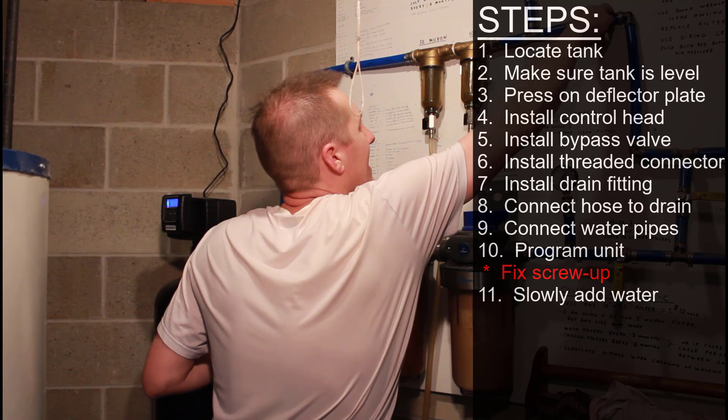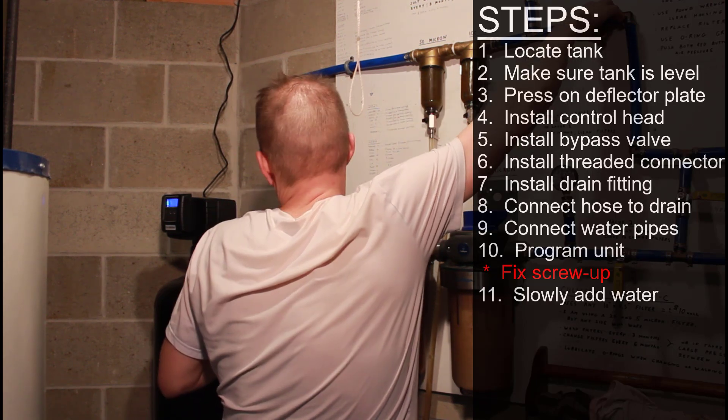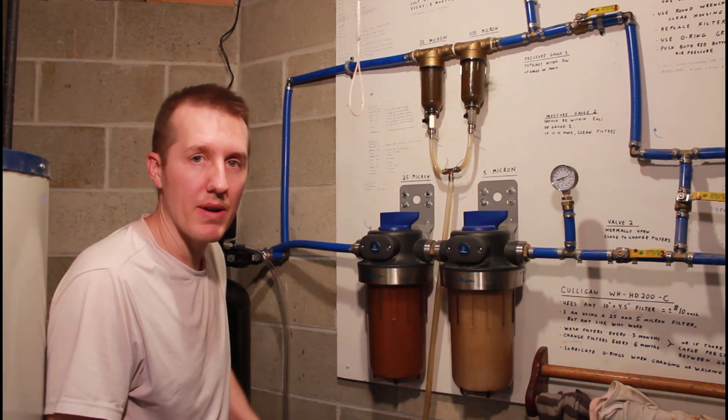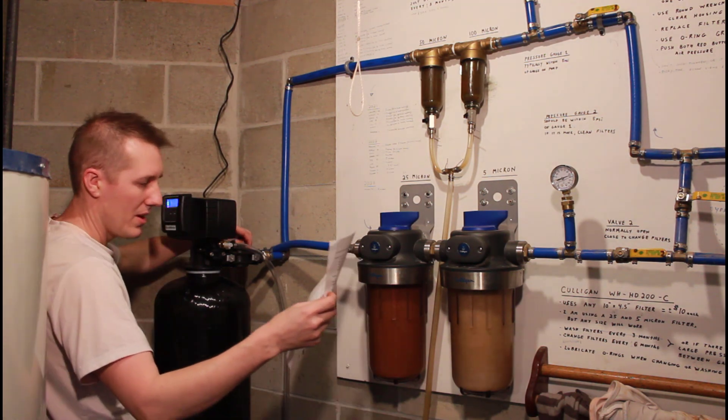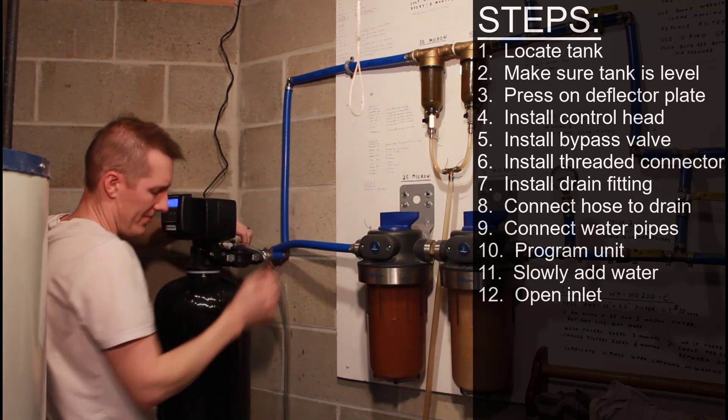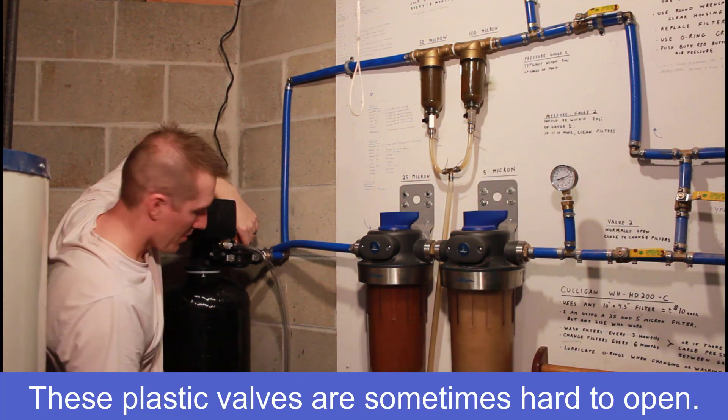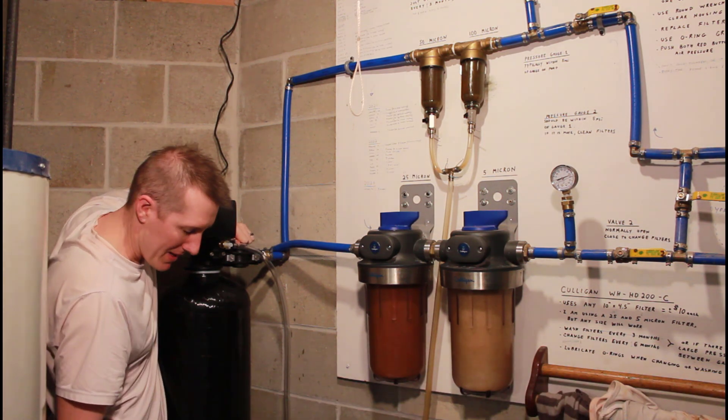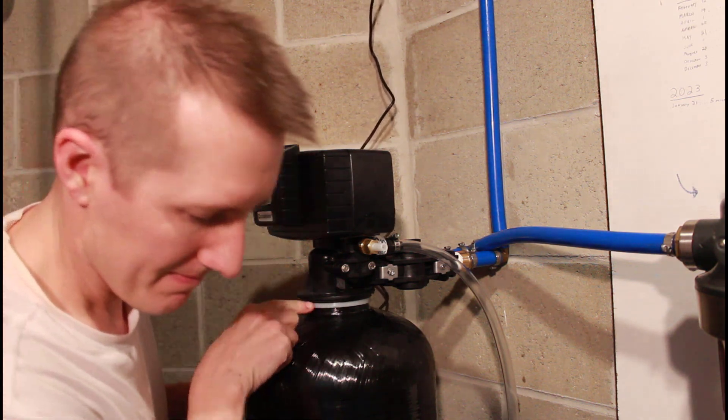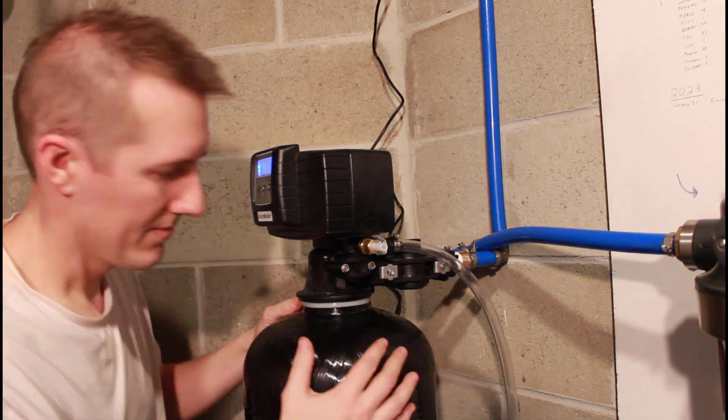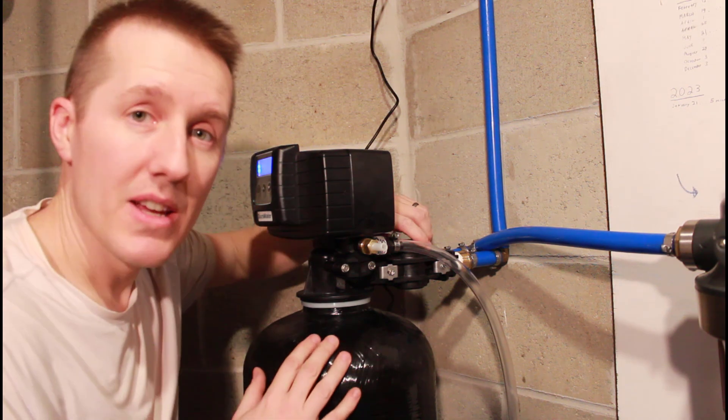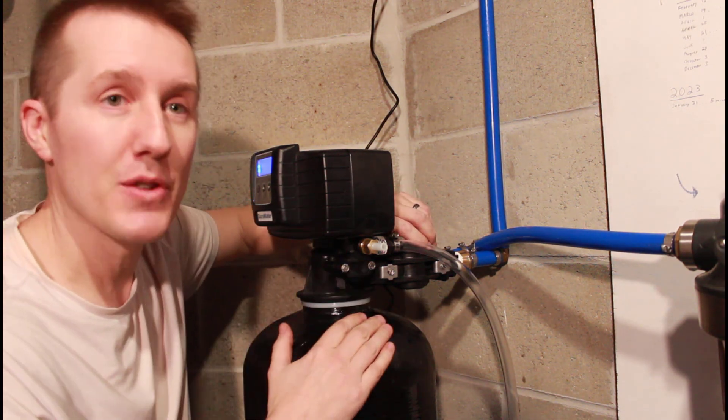Bypasses are closed. Let's add water. I don't see anything leaking, which is great. Every time I use copper, everything leaks. Now we are ready to open the inlet bypass side, which is this one. So slowly opening the inlet bypass side. And I'm going to check when it fills up if this seam holds tight. Okay, I can hear it pretty much full of water. It says, turn the inlet back off and let this sit for 24 hours. So we're going to have to come back tomorrow. I'm just checking and listening, hearing hissing noises, making sure that's all as it should be and nothing's leaking out.